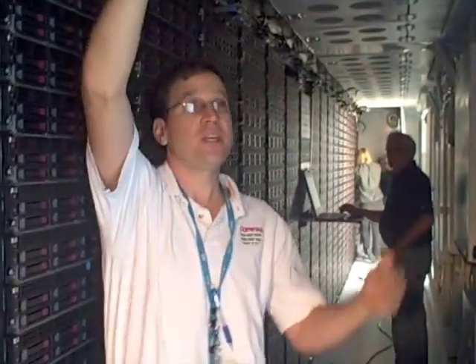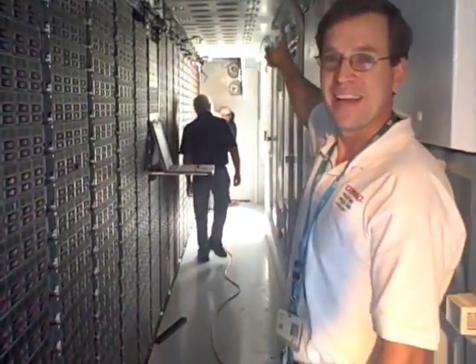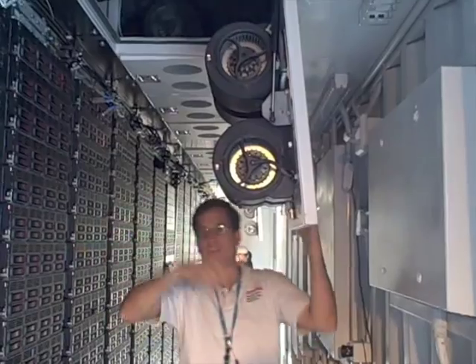The technology we're using includes our modular cooling system and our liquid cool racks. We took the blowers — you can see there's a blower tray hanging down on the end there — so that the blowers are serviceable. If a blower needed to be repaired, you just unscrew it, close it up, put it back in. The heat exchangers are serviceable too. One of the cool things about the heat exchangers is because we're closely coupled, we can actually use 65-degree water, which is pretty warm, and the facility doesn't have to use a chiller at all.